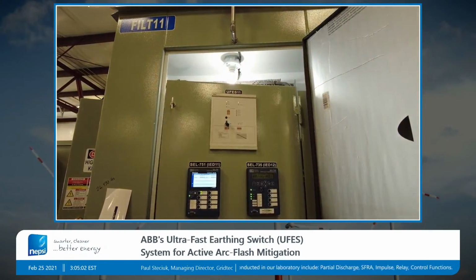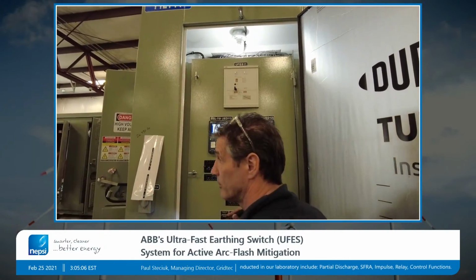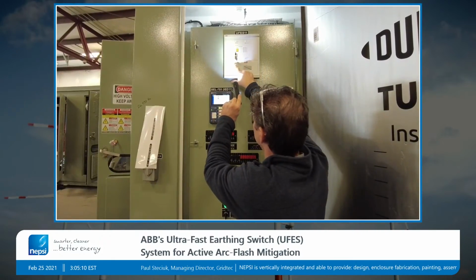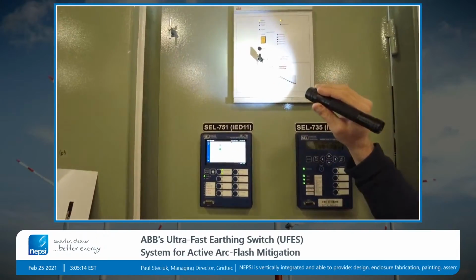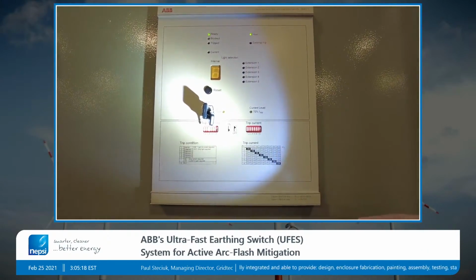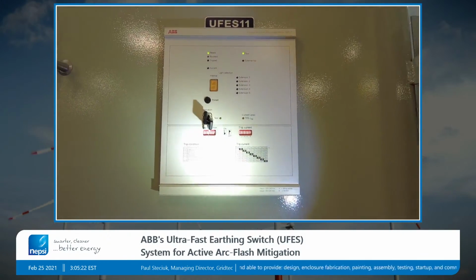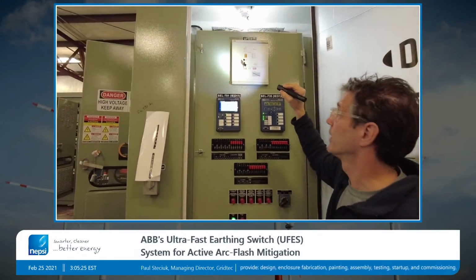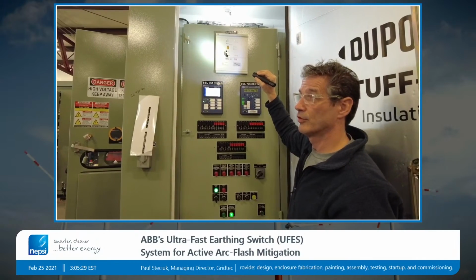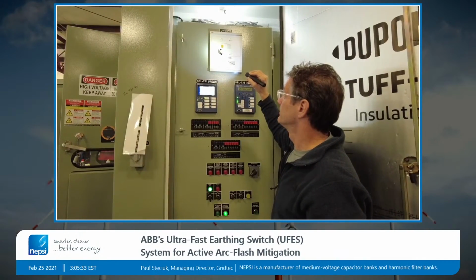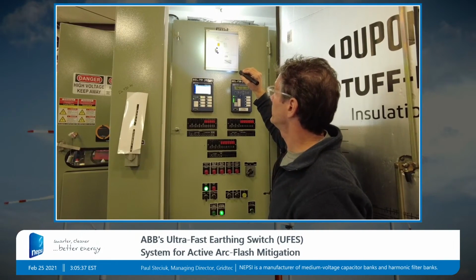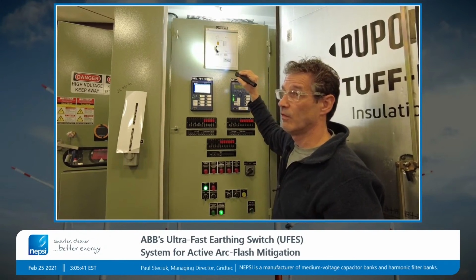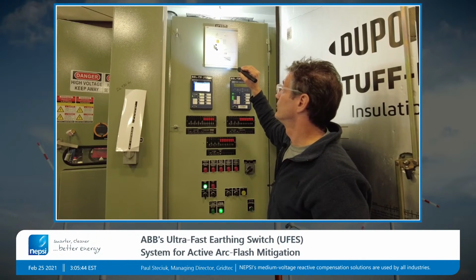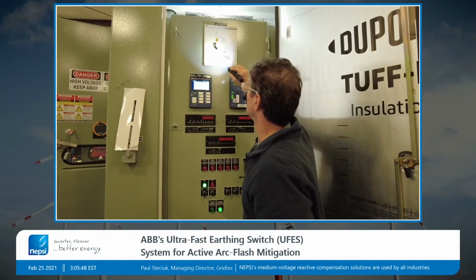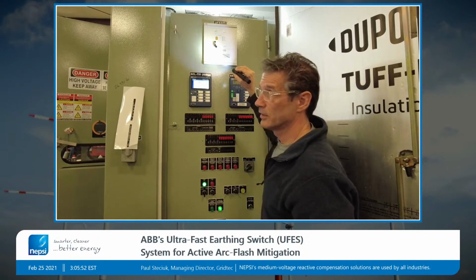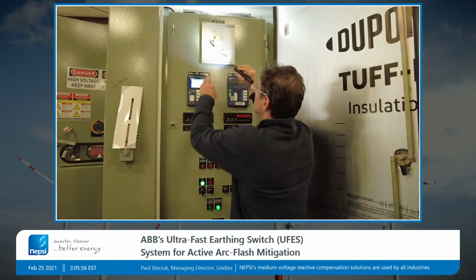Setting up the relay itself is quite simple. It's all done with dip switches. There's no program required. There are trip conditions, and we generally use light and current. We generally use both light and current for switching. We want to make sure that there is some current flow before we actually trip. We normally set that just above the nominal current rating of our bank, so that the bank has to be on. And with that current, we also require to see light, and with the 2 conditions the primary elements can actually switch. You can also just do light only as an option. So that's the setup with the dip switches.